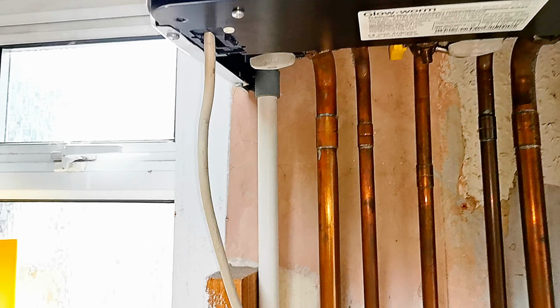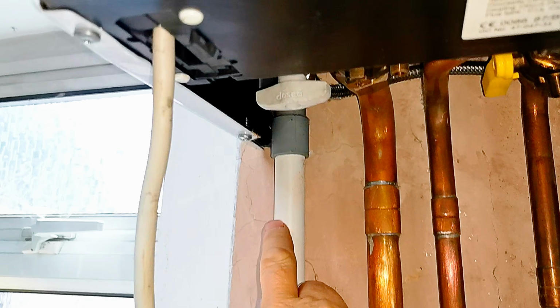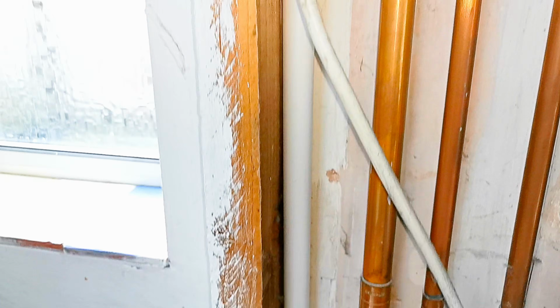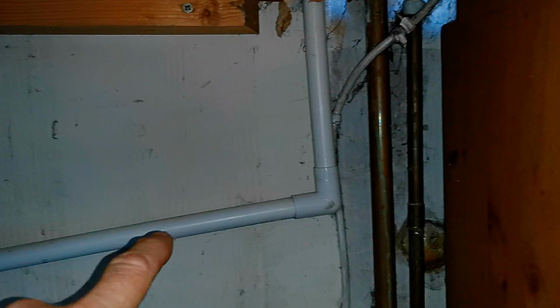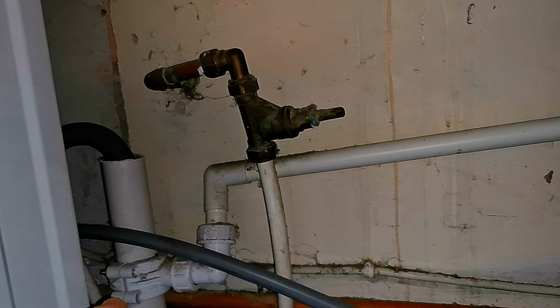So when your boiler is running and the flame is on, it will be producing wastewater all the time, which is running down through the heat exchanger, usually into some sort of trap. And of course that wastewater needs to be disposed of.